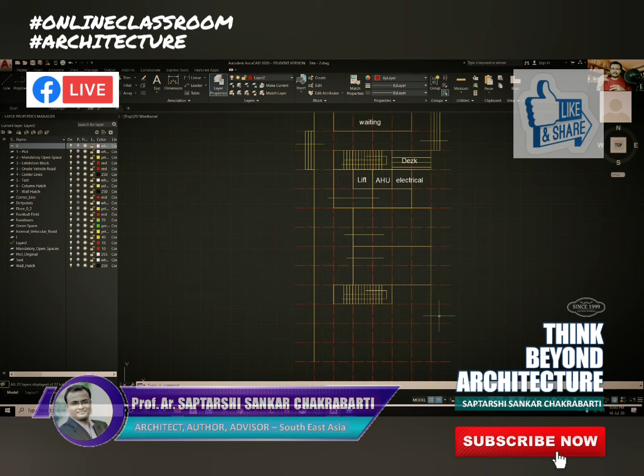Yeah. So a minimum of one. It should be outside. Okay, so I should provide at least one exposed staircase towards the external side, right? Yeah. And if I provide that, is it necessary to provide other staircases that are attached to the external wall? See, there will be a minimum number of staircases as per the travel distance, as per the fire norms. I think it's around 14 meters. Every 14 meters there should be a staircase. At least one of those staircases should be attached to the outer facade or maybe exposed completely. The rest is fine.